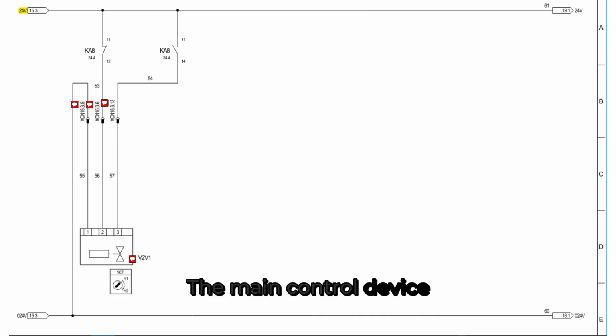The main control device on this page is the relay Ka8, shown near the top left. It operates on 24-volt AC and functions as a low-voltage control relay for the motorized isolation valve. When Ka8 energizes, its contacts close, sending power to the valve actuator to shift position. The relay includes two types of contacts, normally open and NC contacts, labeled 11 to 12 and 11 to 14. These contacts allow the valve to be energized or de-energized based on commands from the controller.